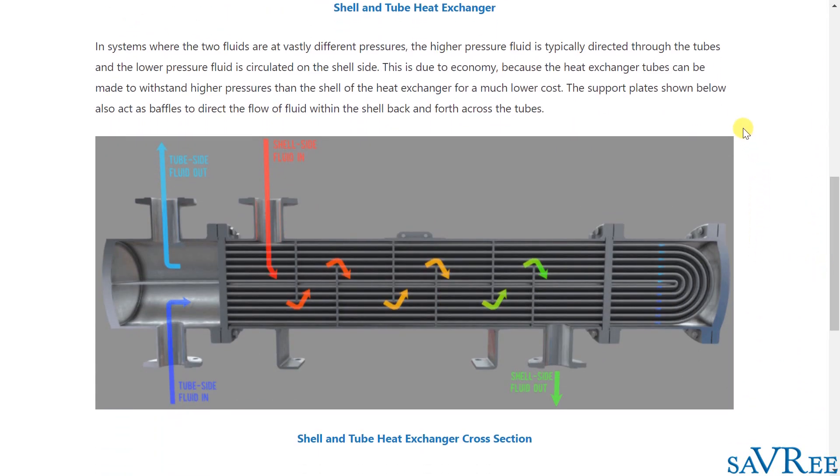In systems where the two fluids are at vastly different pressures, the higher pressure fluid is typically directed through the tubes and the lower pressure fluid is circulated on the shell side. This is due to economy because the heat exchanger tubes can be made to withstand higher pressures than the shell of the heat exchanger for a much lower cost.